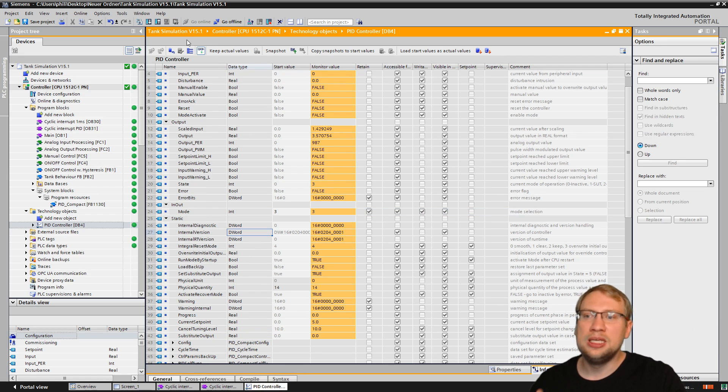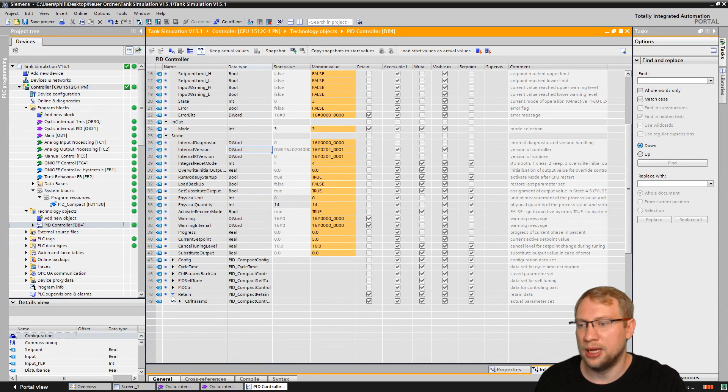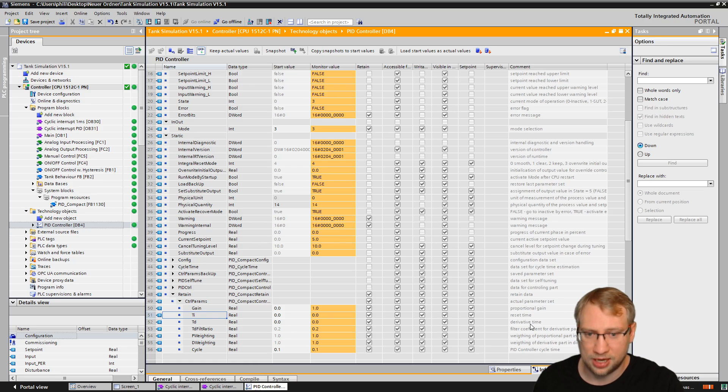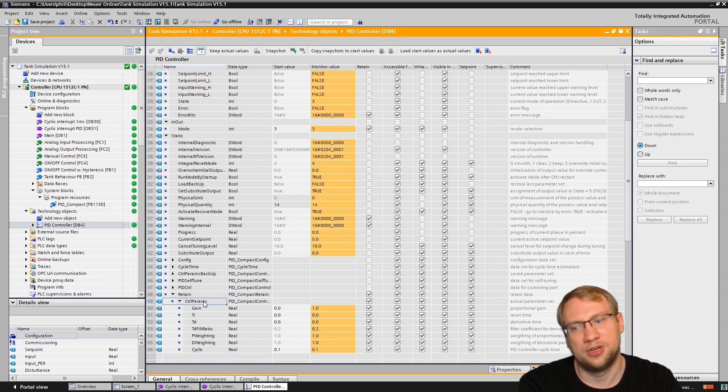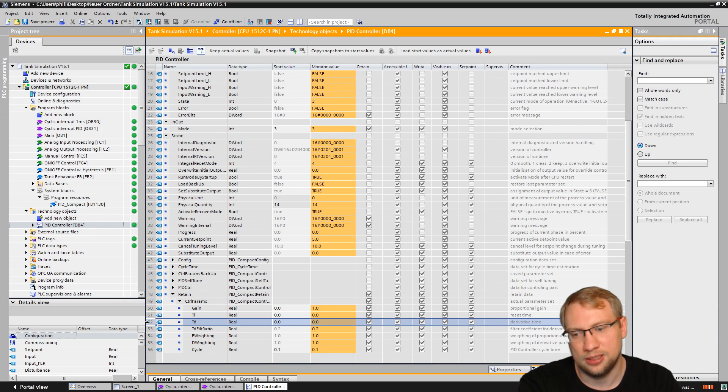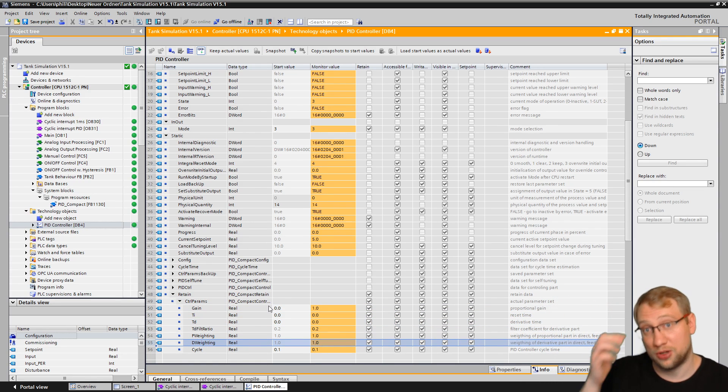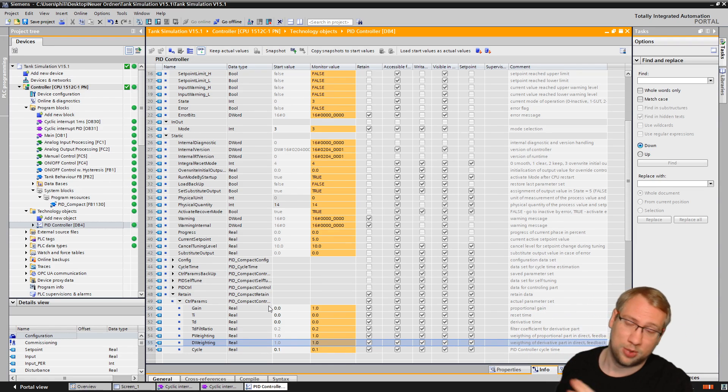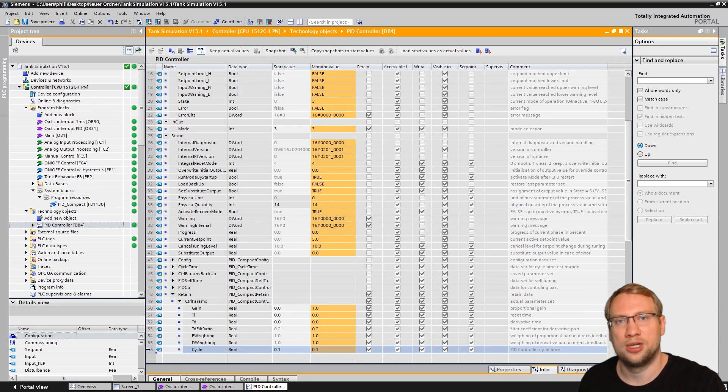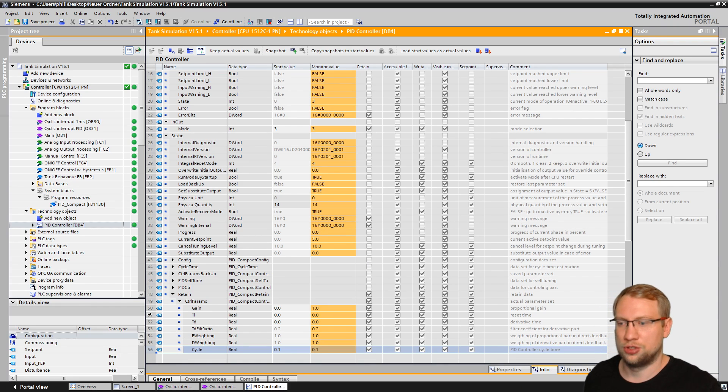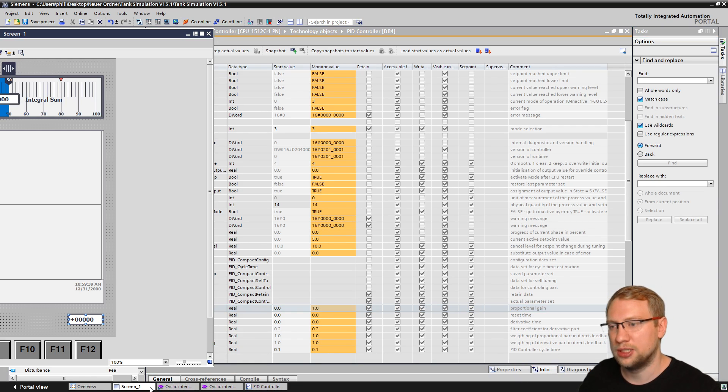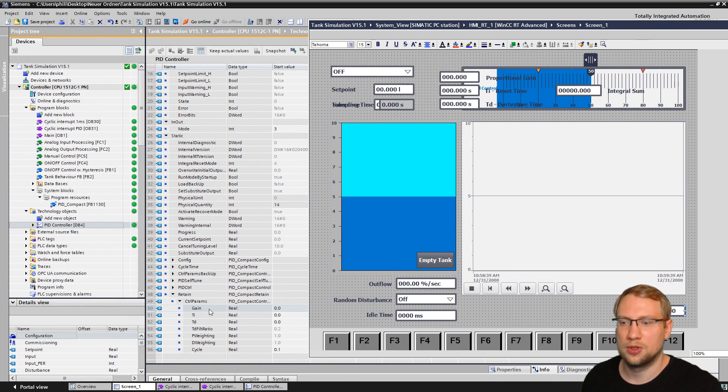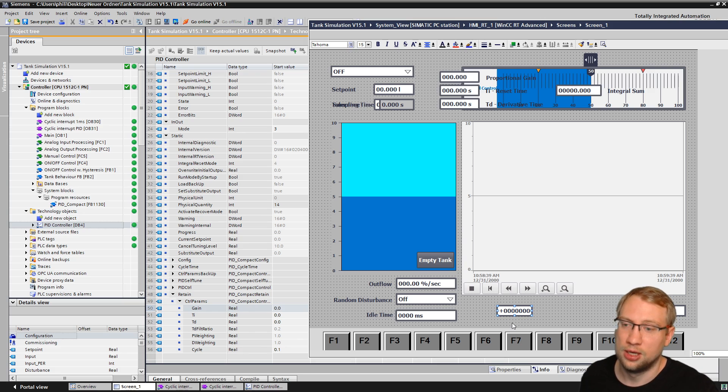If I want the P, I, and D parameters, the proportional gain, the integral time, and the reset time and the derivative time. You can find these in retain and control parameters. And then we have the gain, the TI and TD. You also have the different weightings. Not going to talk about this, this is more control theory. This video is just about how do you find it, how do you use it. And we could also change the cycle time. Right now the cycle time is 0.1, which is I think 100 milliseconds. So every 100 milliseconds it gets evaluated. If I want in runtime to change the proportional gain, for example, that's all you need to do. Get the proportional gain from your data block, open your screen here, just drag and drop that gain on there. And now I've got the proportional gain and I can change it in runtime.